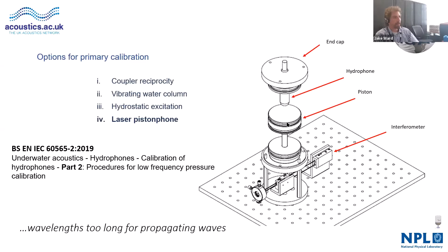So what is a laser pistonphone? It's an acoustic calibration device with a circular piston driving a closed volume of air, and it's widely used in airborne acoustics to calibrate microphones, but here we're using it to calibrate hydrophones. And a key difference there: microphones can't typically tolerate hydrostatic pressure. Their sensitivity is typically higher than a hydrophone's, unless you put an amplifier inside the hydrophone. And NPL's been working on this. There's a paper in Metrologia, 2007. Richard Byram is a collaborator on this project, and used to work at NPL and published this work on laser piston phones for microphone calibration.